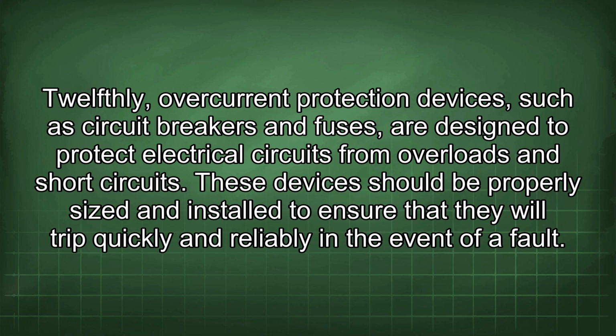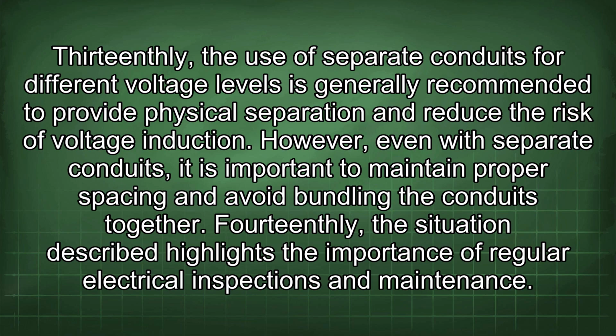These devices should be properly sized and installed to ensure that they will trip quickly and reliably in the event of a fault. 13thly, the use of separate conduits for different voltage levels is generally recommended to provide physical separation and reduce the risk of voltage induction. However, even with separate conduits, it is important to maintain proper spacing and avoid bundling the conduits together.